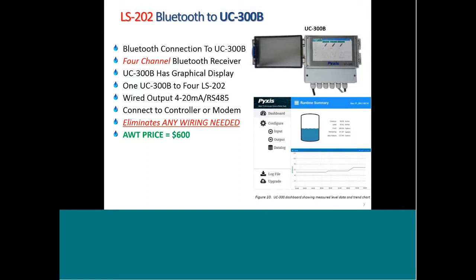One is a graphical display of each tank, of inventory and usage. It also offers 4 to 20 and Modbus output so that it can be directly wired to a controller. And it offers a Bluetooth interface so it can take the signal remotely from the tank level monitor. But most importantly, it also offers an Ethernet direct drop for a modem in the event that you want to use this as a gateway to a data management system.